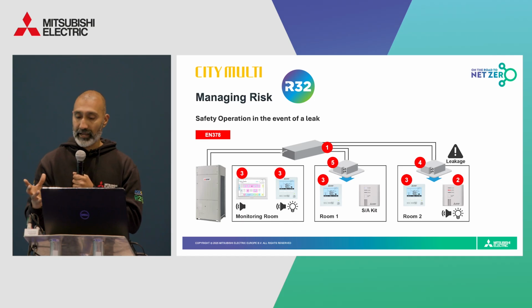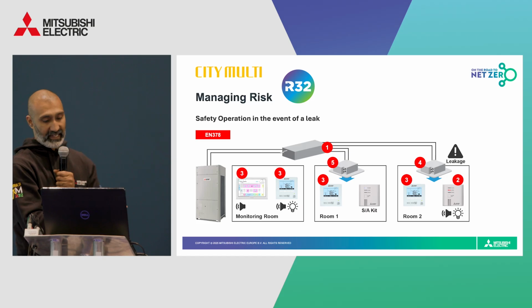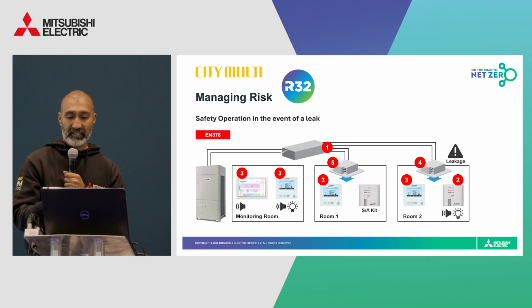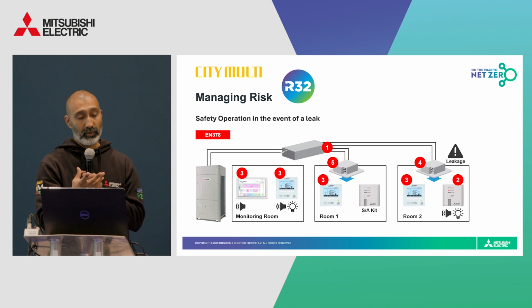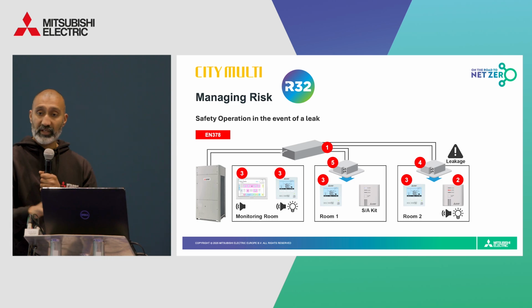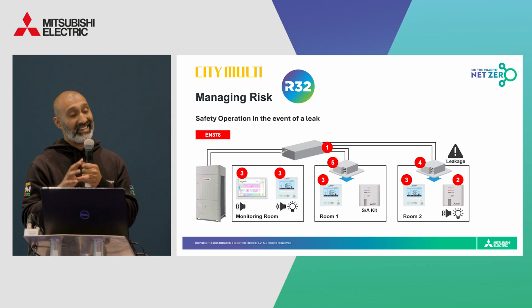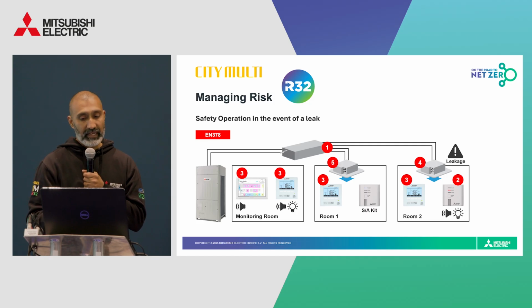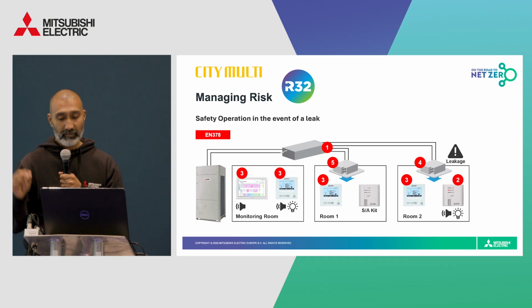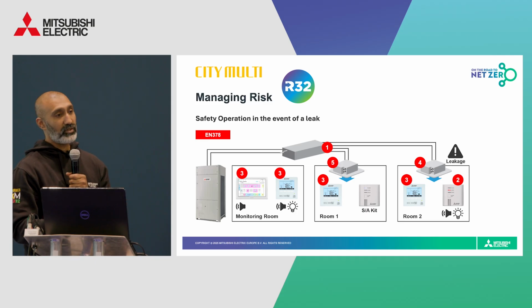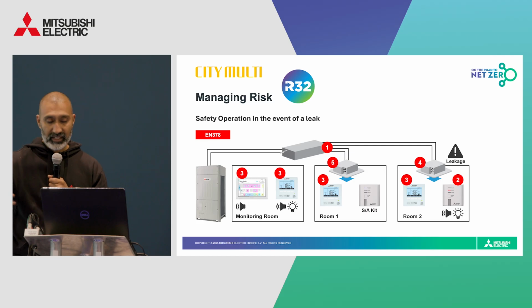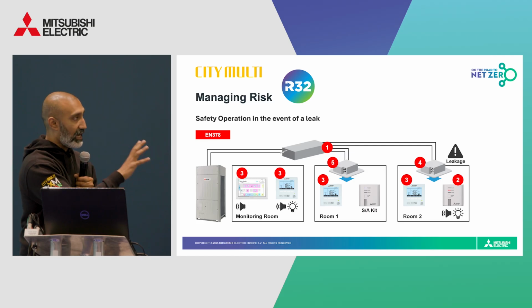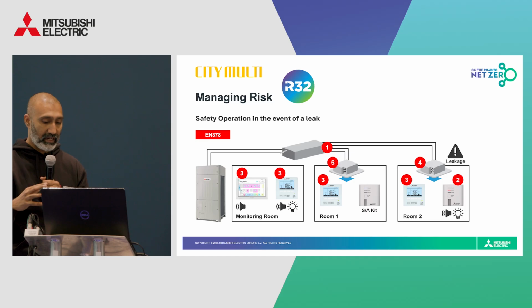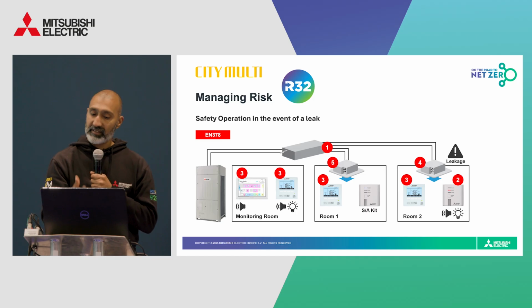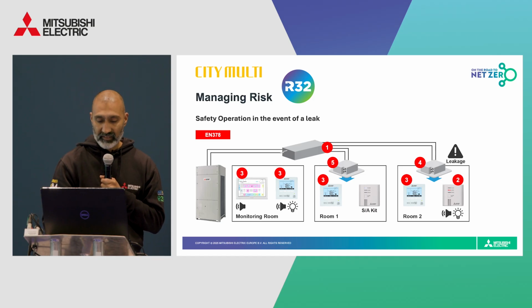an independent power supply. So if a leak is detected, the shutoff valve at the BC box closes and the sensor and alarm kit provides an audible and visual alarm. All the remote controllers and the centralized controller will show an error message and the address of that affected indoor unit. The centralized controller will also sound out an alarm, and the affected indoor unit will actually stop operating whilst all the others continue to work. And importantly, our detectors have a 30-year lifespan compared to just 10 years for many current R32 competitors. And again, this means fewer replacements, lower operational costs, and I guess greater peace of mind for our clients.